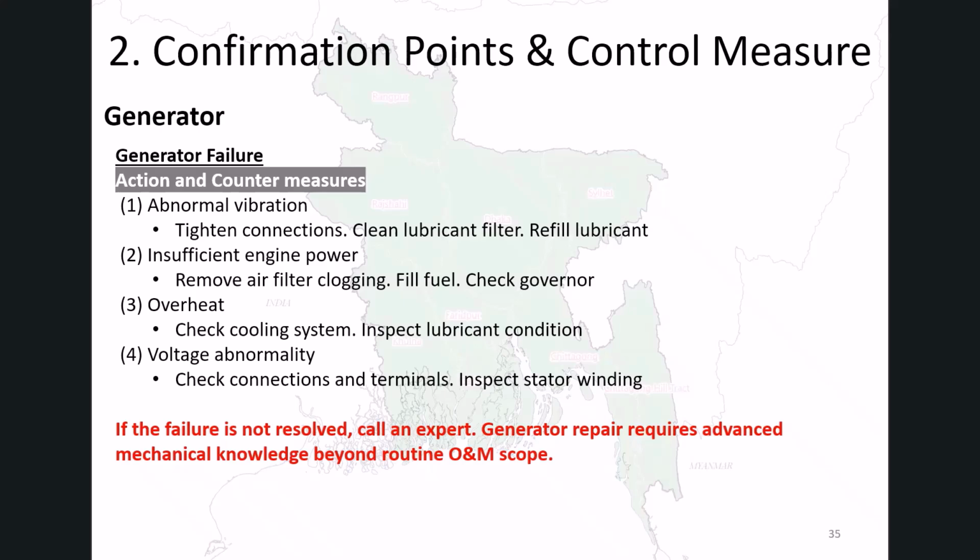Third, overheating. If overheating occurs, the cooling system should be inspected immediately. Operators should also check the lubricant condition because insufficient or degraded lubricant can increase engine temperature. Continuous overheating may cause serious damage to engine components and generator parts.